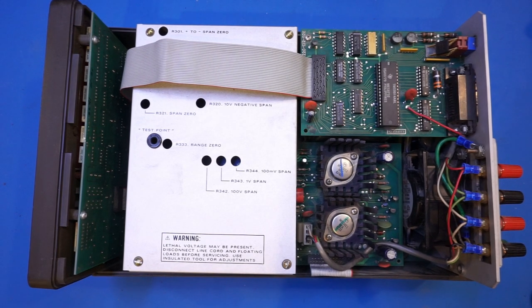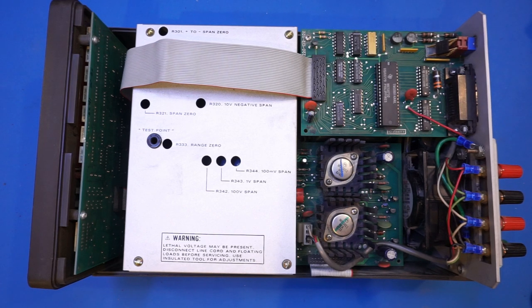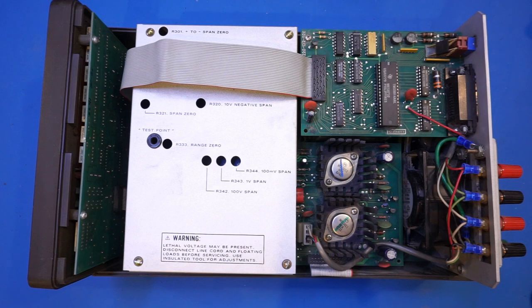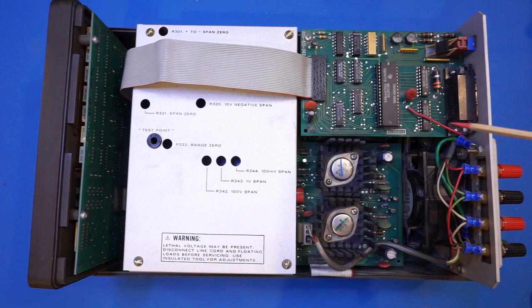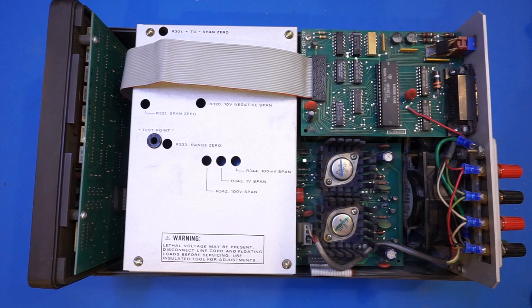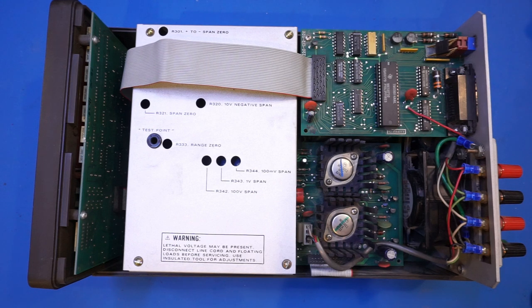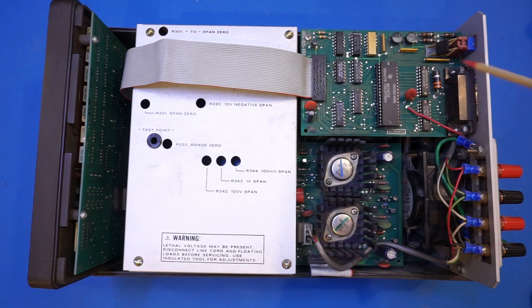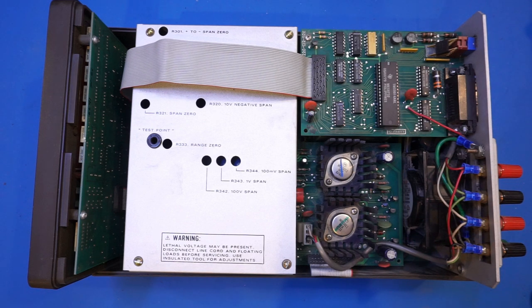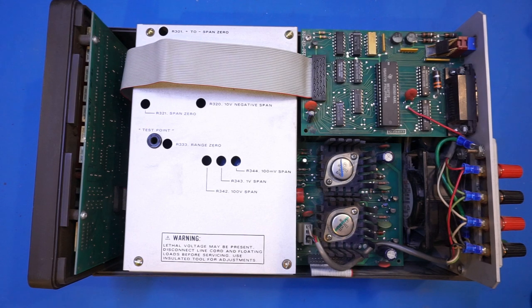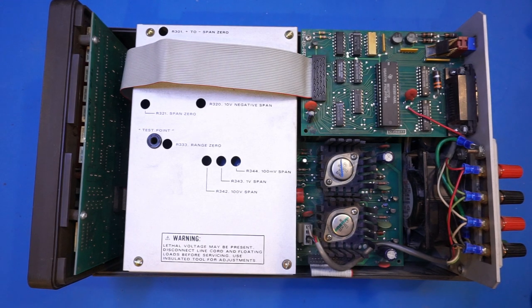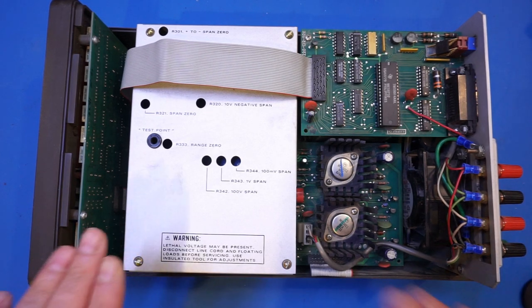And when we talk about a voltage source, when you think about it, the basic operating principle is actually not that complicated. All it takes is really a precision voltage reference outputting an adjustable voltage. And in this case, it's handled by a digital to analog converter. And then we have an output stage to generate the required voltage under load. And so in this case, it's done in a bootstrapped op amp so that the output can handle from 100 volts to minus 100 volts in that regard. It can swing between the two voltage rails.